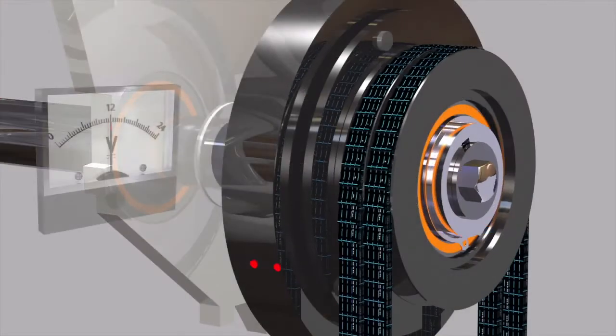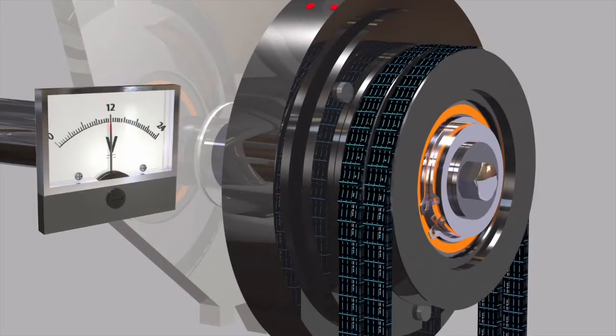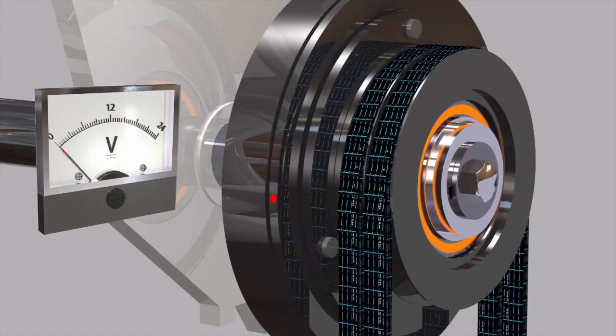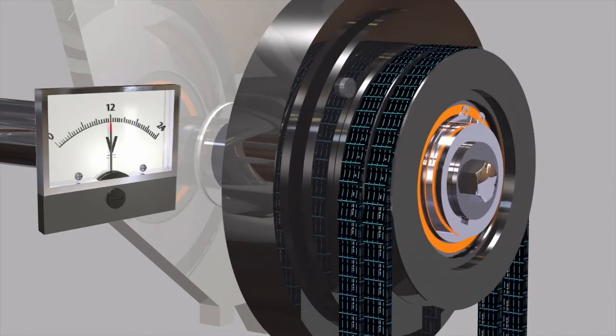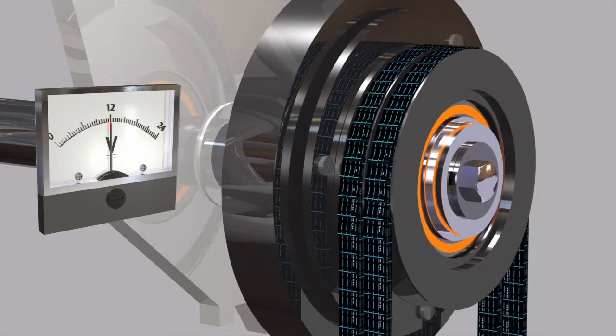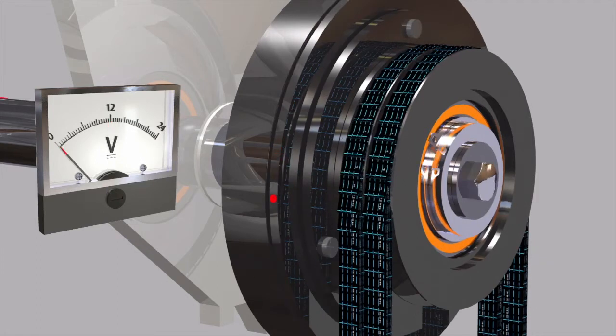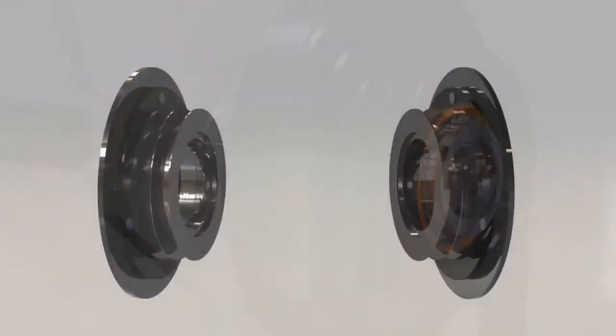The magnetized rotor and armature attract each other. The clutch slips for a very short time on initial engagement. The time depends upon the speed and the inertia being accelerated. The torque is transmitted from the rotor to the armature and into the leaf springs driving the hub or pulley. When the clutch is fully engaged, there is no slippage and the torque transfer is 100 percent efficient.